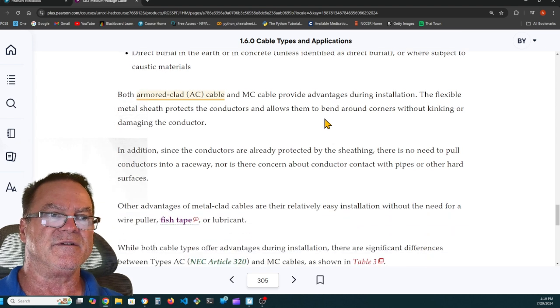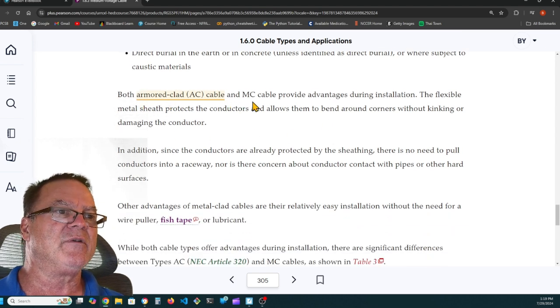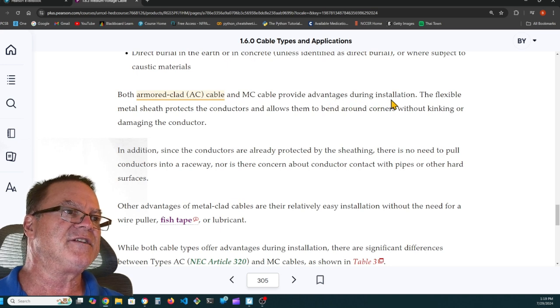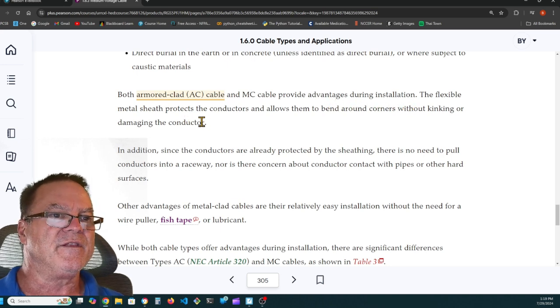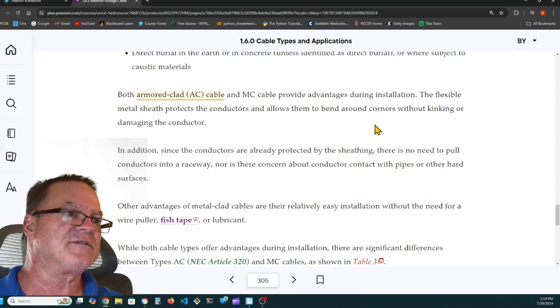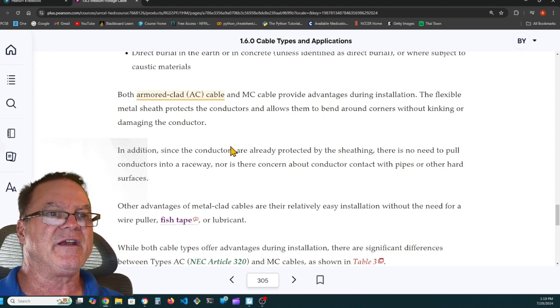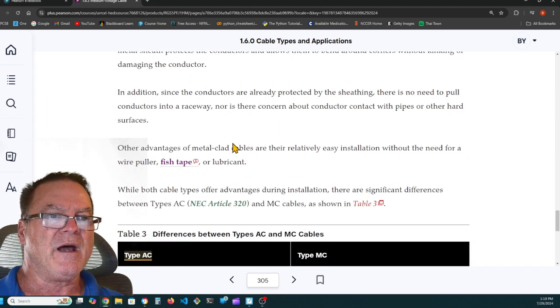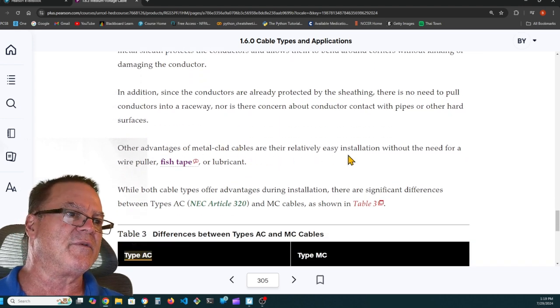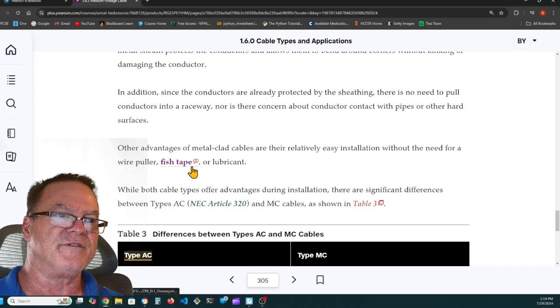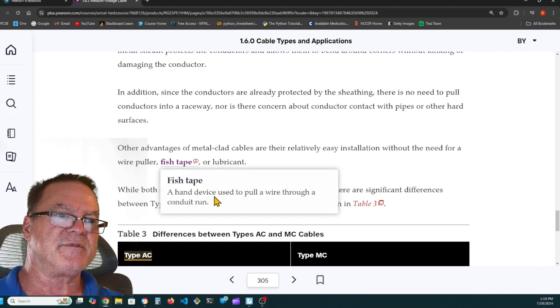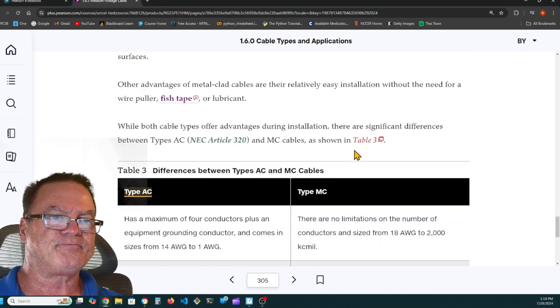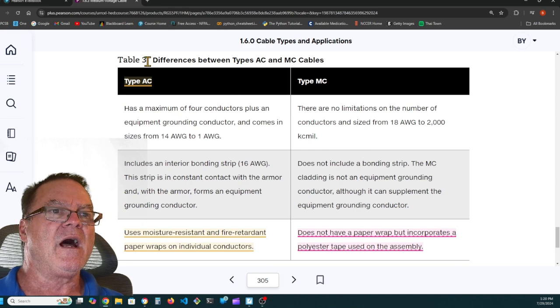Both armored clad cable and MC cable provide advantages during installation. Flexible metal sheath protects the conductors and allows them to bend around corners without kinking or damaging the conductors. Other advantages of metal-clad cables are their relative ease of installation without the need for wire puller, fish tape, or lubricant. A fish tape is a hand device used to pull wire through a conduit run. Table 3, differences between types AC and MC cable.